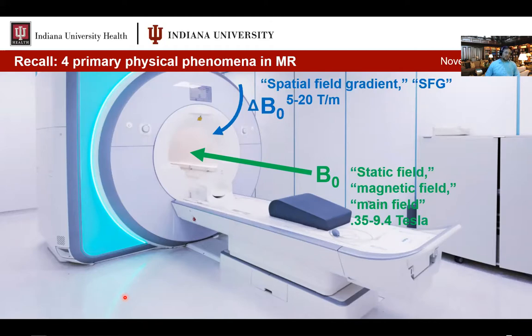All scanners also have a spatial field gradient. Again, we talked about this. This is where the field is changing across space. So we call this delta B0. This is usually in a range of 5 to 20 Tesla per meter. It can be higher in some cases. It does scale up with the magnetic field. So our 9.4 Tesla scanner does have much higher spatial field gradients than our permanent magnet, or open magnet, I should say, that we have in the beltway.